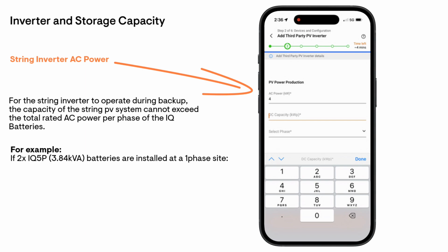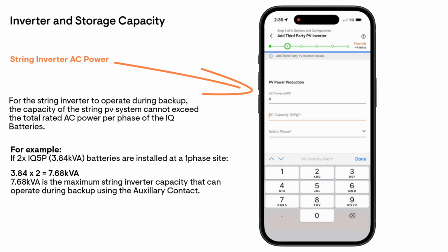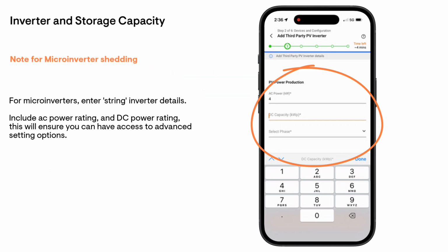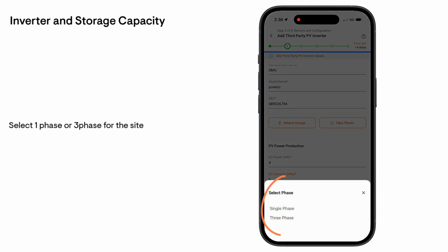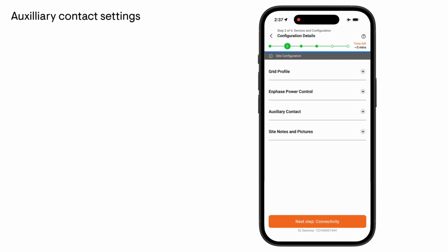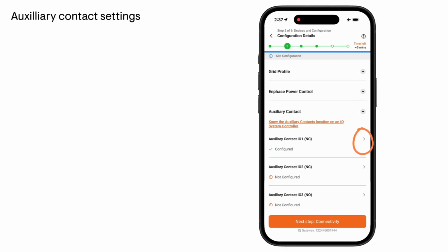For example, if 2 IQ Battery 5P units are installed, the maximum string inverter capacity permitted to operate during backup is 7.68 kVA. If solar production is expected to continue during backup operation, verify the string inverter capacity during site assessment and size the battery system accordingly. Select the appropriate phase configuration and proceed to configure the auxiliary contact settings.